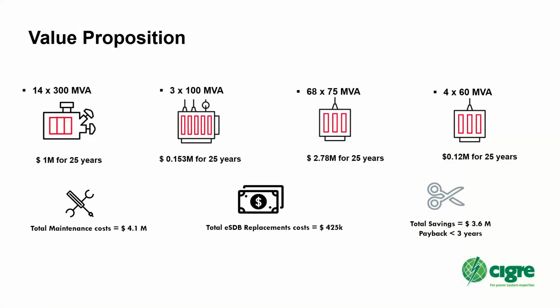When we scaled this up for one particular utility, they had about 14 300 MVA transformers, 68 75 MVA transformers, and 4 60 MVA transformers. We calculated the total maintenance cost over a 25-year period just to maintain, replace, and dispose of silica gel, and it came out to around $4.1 million. When we replaced it twice over the same period with a self-dehydrating breather, it cost around $425,000. The savings are around $3.6 million, with payback in less than 3 years. So there's a very good return on investment if we adopt maintenance-free, self-dehydrating, or smart breathers.